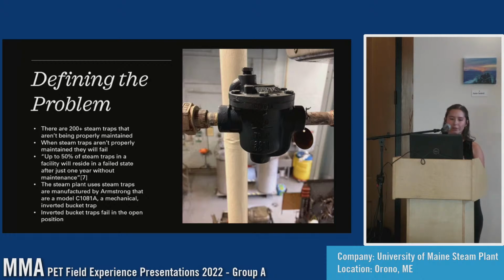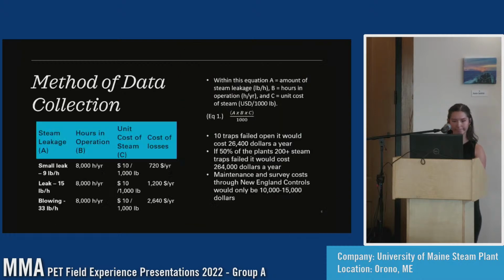So a direct quote from my technical analysis is up to 50% of steam traps in a facility will reside in a failed state after just 1 year without maintenance. The steam traps that we use at the steam plant are manufactured by Armstrong, and they are inverted bucket traps, which are mechanical. They tend to fail open, which will blow steam and essentially just move our production costs up, and it's a waste.